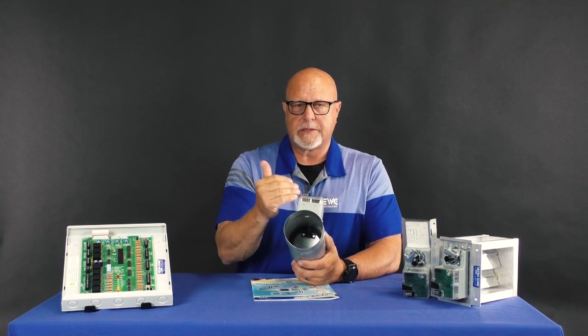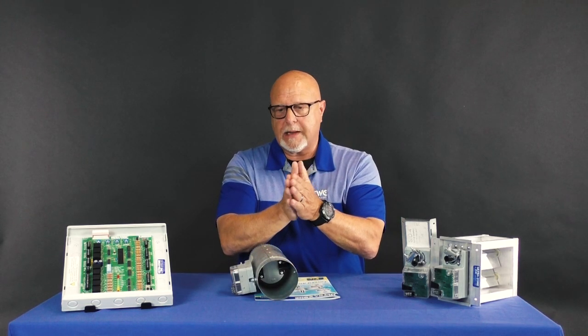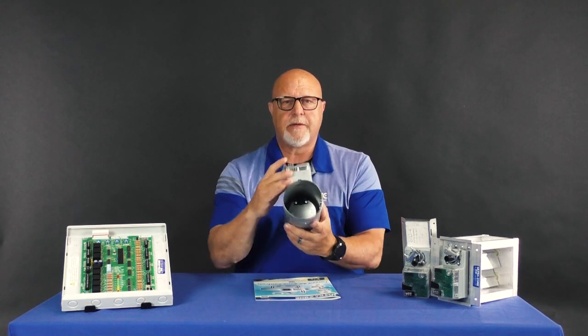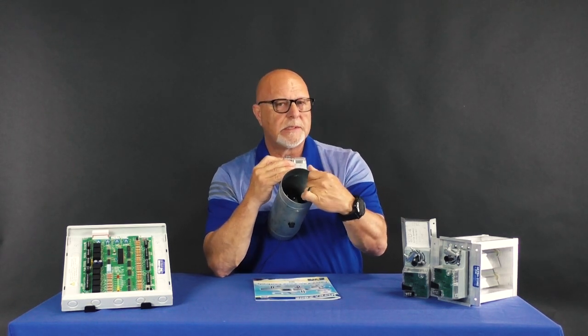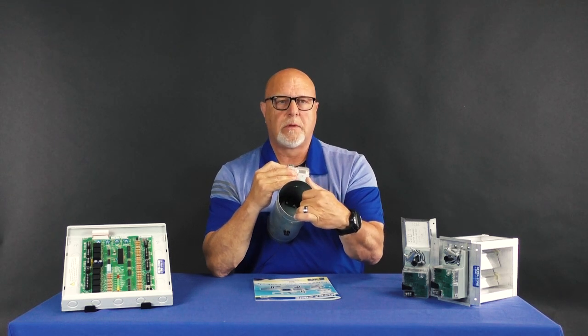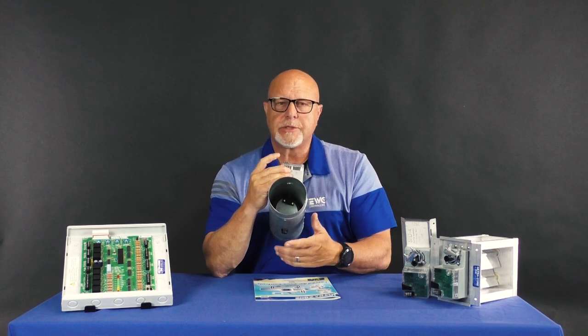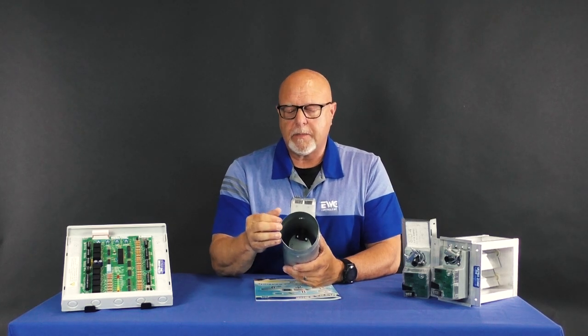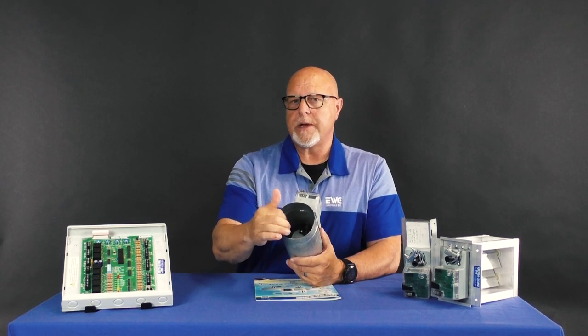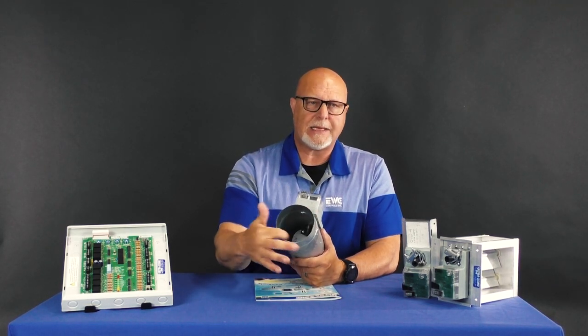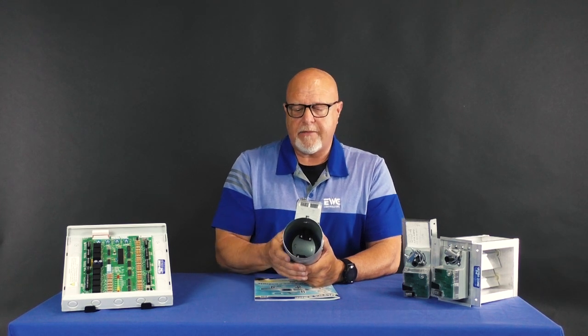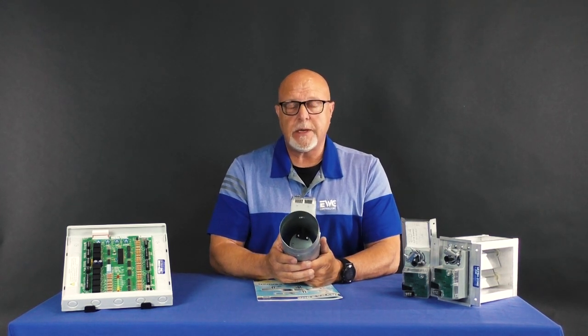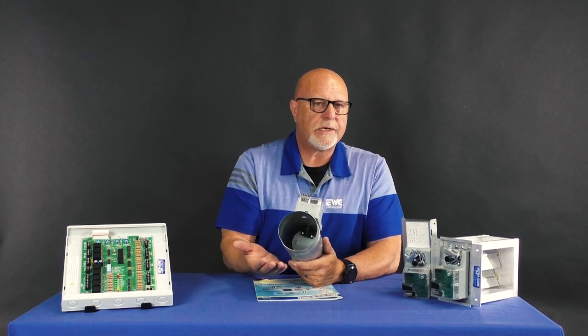We've put this pour-on cellular foam gasket actually between two pieces of galvanized sheet metal, and the gasket moves with the shaft, making a very nice tight seal, and can compensate for a not so round damper. This also makes it a very important step in innovation, because now we are not restricting the airflow with a gasket. My competition, like I said, they glue a gasket on the internal side. If I have a 4-inch damper, as I'm showing here, and a 1/2-inch gasket inside of here, ask yourself, do I have a 4-inch damper anymore?